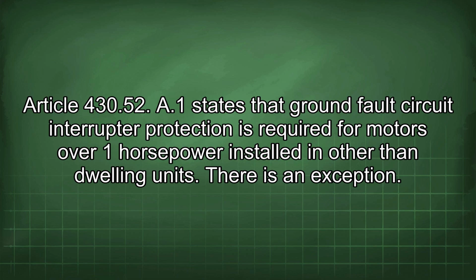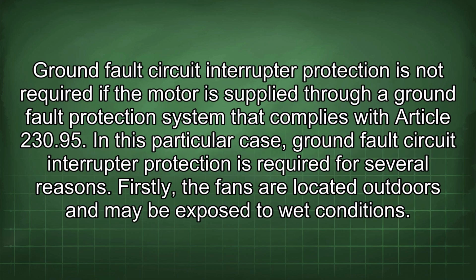Article 430.52 A1 states that ground fault circuit interrupter protection is required for motors over 1 horsepower installed in other than dwelling units. There is an exception. Ground fault circuit interrupter protection is not required if the motor is supplied through a ground fault protection system that complies with Article 230.95. In this particular case, ground fault circuit interrupter protection is required for several reasons.